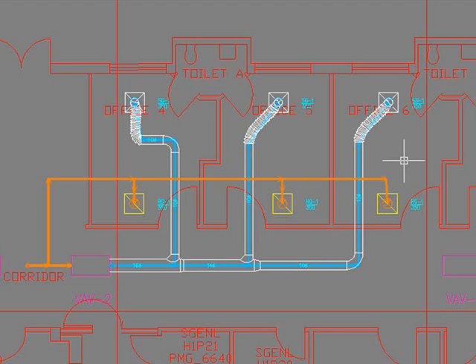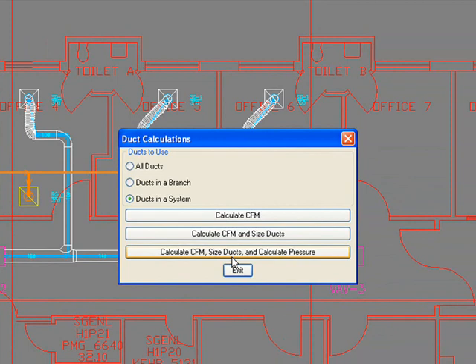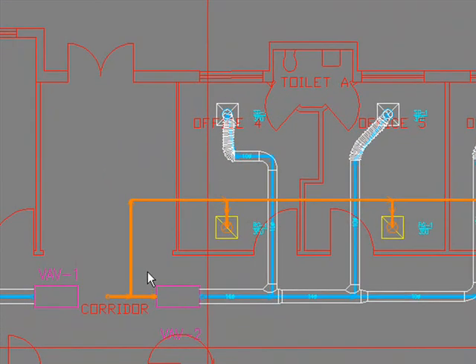We've done our return ductwork and I want to size it. I'm going to hit my calculate button and ask the program to do the calculation. The client has given me the criteria of how to size my ducts with 0.08 inches pressure drop per 100 feet. They've given me the feet per minute velocity on my supply and return ducts. For supply they've given me 1100 feet per minute and for return 900 feet per minute. Those I already input as default values in the program. All I have to do is hit the calculate button and watch the program do its drafting work.